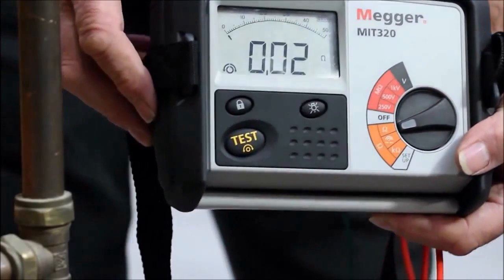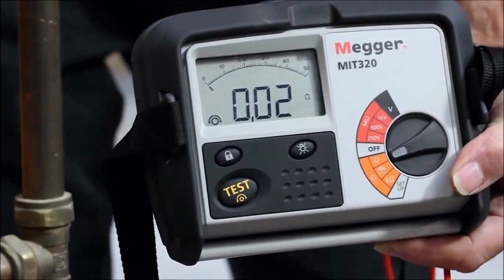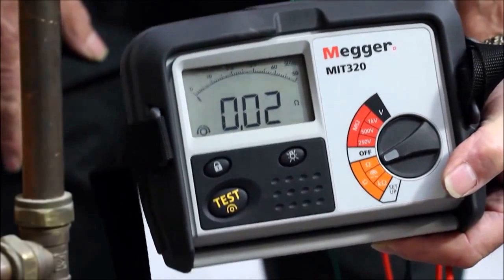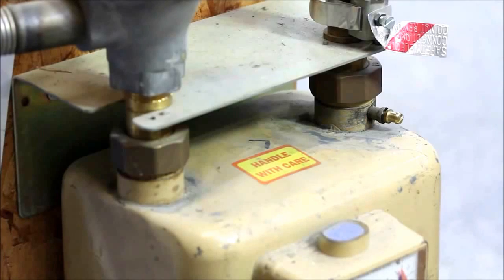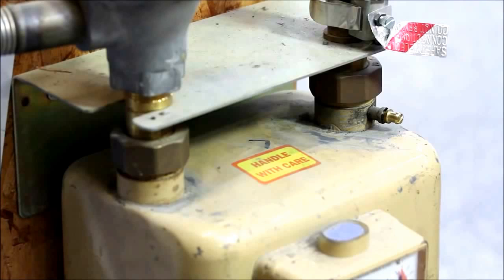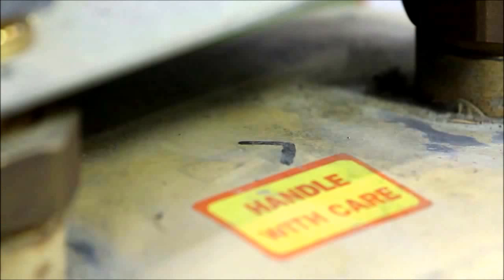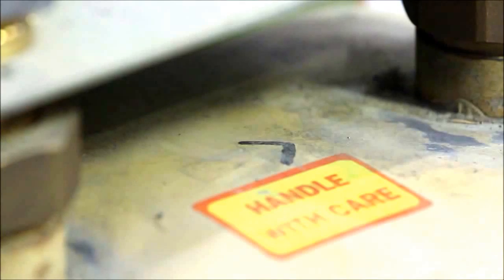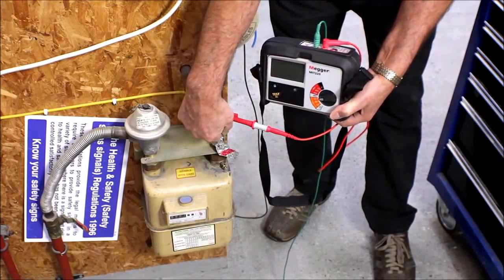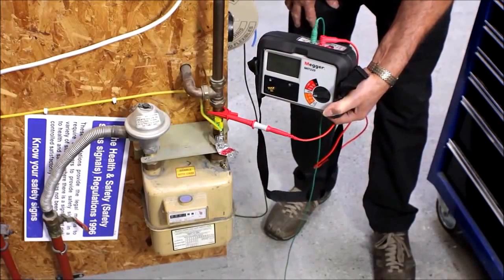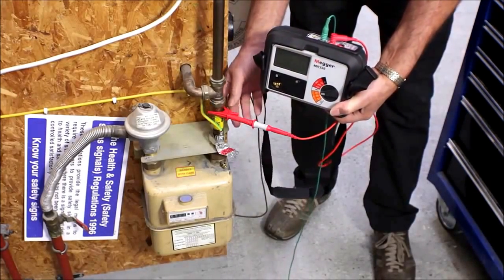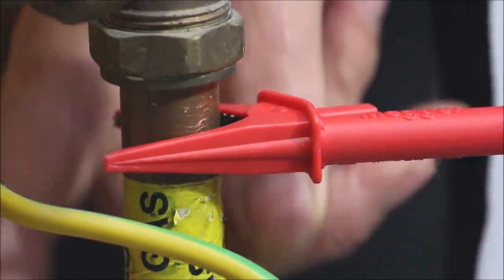One other good thing, which is a bit of a tip: sometimes as electricians we're not sure which side to connect the bonding conductor. If you look on the top of a gas meter, there's generally a chevron or an arrow. It's not really there to help electricians, but it can be. If you connect your bonding conductor on the side that the arrow is pointing to, you're never going to be wrong. And also of course, we need to make sure that the clamp is before the first joint.